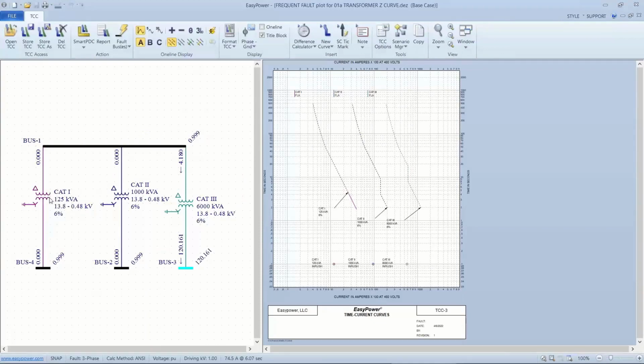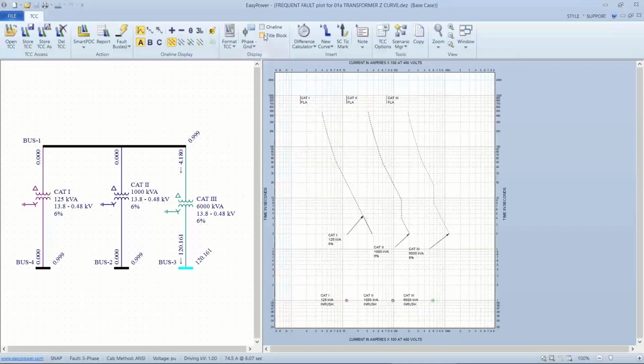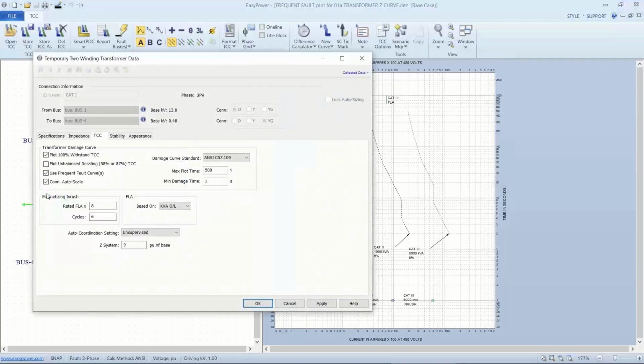And in this case, they're color coordinated. I'm not sure you can see that on the screen. So real briefly, what's noticeable right off the bat is that this is a straight line, and this is a square, what's loosely referred to as a Z curve with a jag in the middle here. This is referred to as a frequent fault curve versus the Cat 1 transformer, which doesn't have, by definition, frequent fault curve availability.